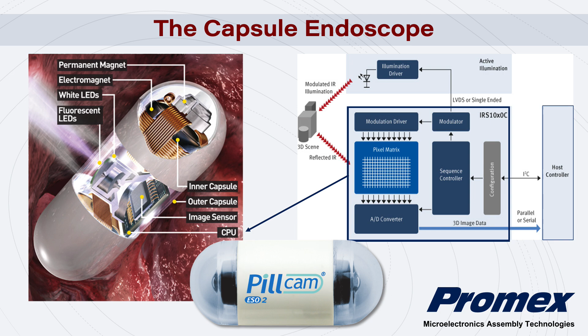And this is a more extraordinary version of the concept, a capsule endoscope, made with all the optics, image sensors, and electronics stuffed into it that a person literally swallows. And this device goes through the intestinal system and sends out either an RF signal or records a video record internally of what the image looks like as it passes through the digestive tract. So such a device must have a series of unique characteristics. It has to be able to be assembled, be very robust, and take some amount of physical and mechanical abuse. And it needs to withstand sterilization.